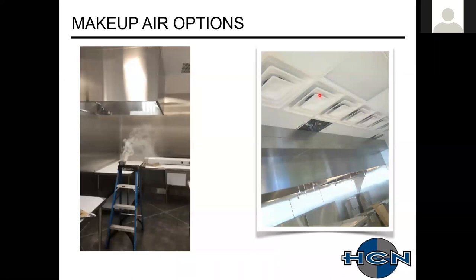Picture next to it, they had a good idea. They want to bring some rooftop air into the space to cool those kitchen cooks, keep them nice and comfortable. Problem with that is with four-way diffusers, high discharge, what typically happens is this is going to throw air right into the makeup air. It's going to mix, and what usually happens is it pulls off and doesn't get sucked back in, but rolls off and diffuses into the space, so causing a little bit more harm than anticipated and increasing your makeup air diffusion into the kitchen environment.